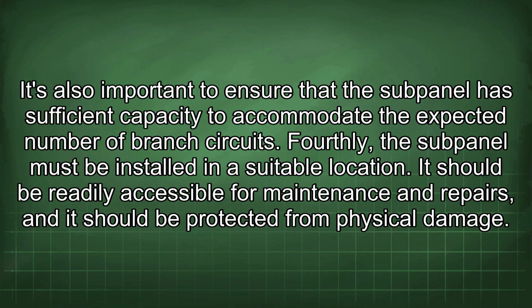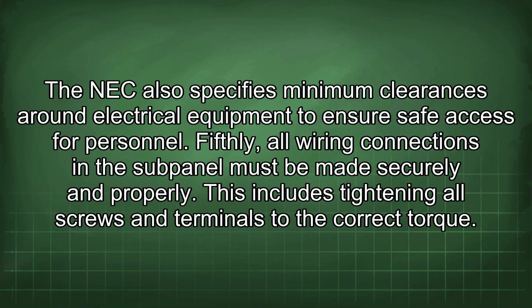It's also important to ensure that the subpanel has sufficient capacity to accommodate the expected number of branch circuits. Fourthly, the subpanel must be installed in a suitable location. It should be readily accessible for maintenance and repairs, and it should be protected from physical damage. The NEC also specifies minimum clearances around electrical equipment to ensure safe access for personnel.